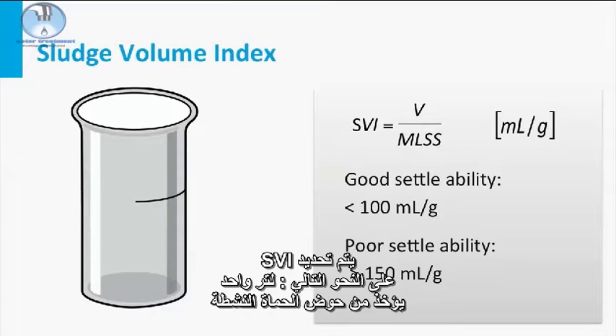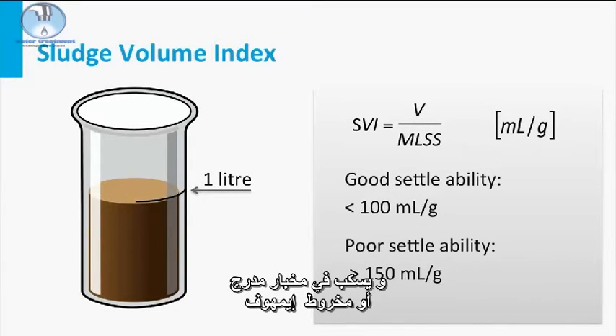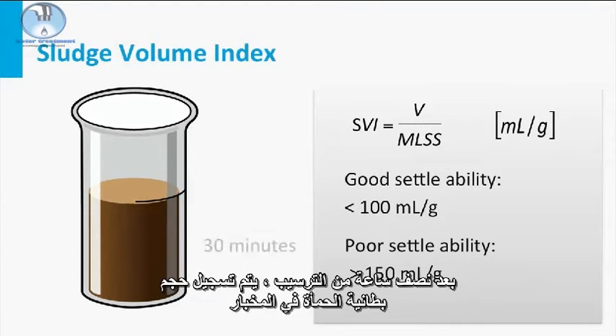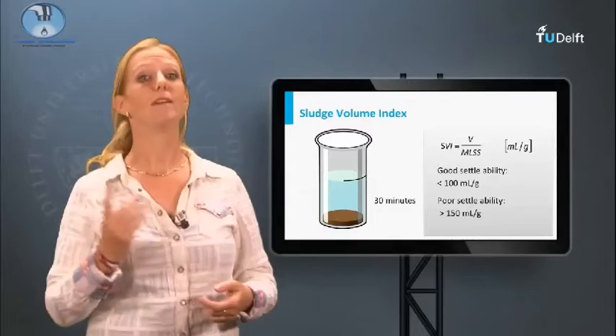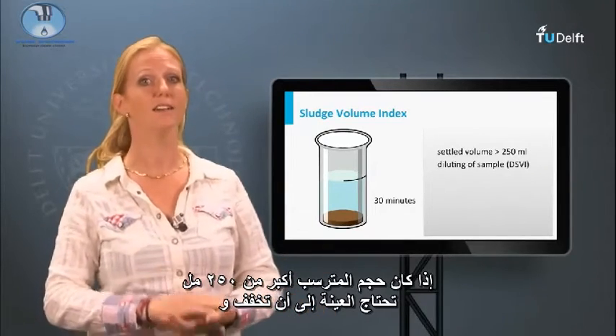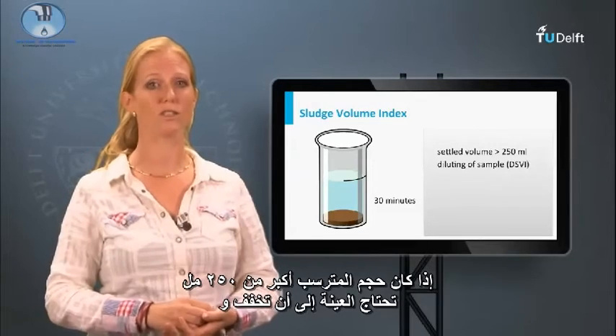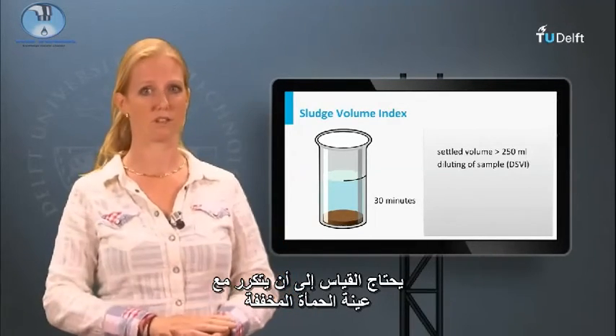The SVI is determined as follows. One liter of mixed liquor is taken from the activated sludge tank and poured into a measuring cylinder, or Imhof cone. After half an hour of settling, the volume of the sludge blanket in the cylinder is registered. If this settled volume is larger than 250 milliliters, the sample needs to be diluted, and the measurement needs to be repeated with the diluted sludge sample.